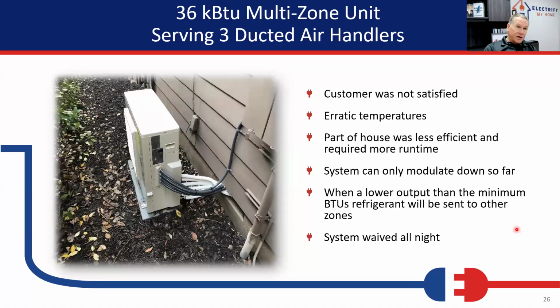They did not take those down to the studs. They just painted them up. So they didn't put new drywall on, they didn't insulate the outside walls. They did have matching windows, but I made an assumption that the whole house was tight. So I designed it with a 9,000 BTU ducted for the two bedrooms on the end. I'm like, that's going to be plenty for that.